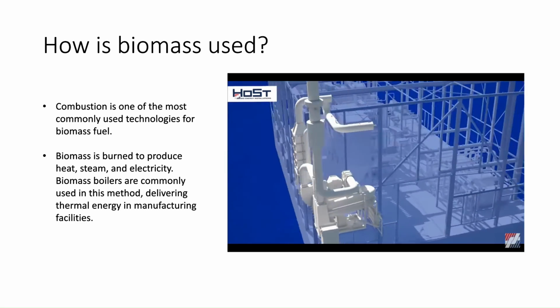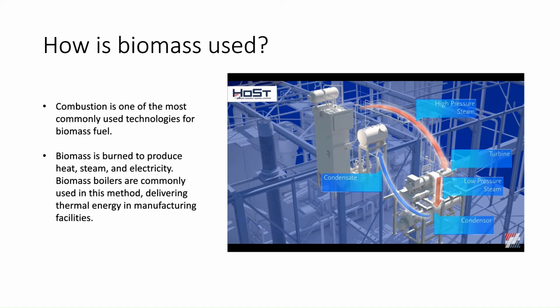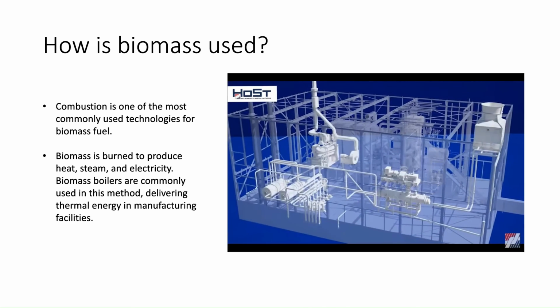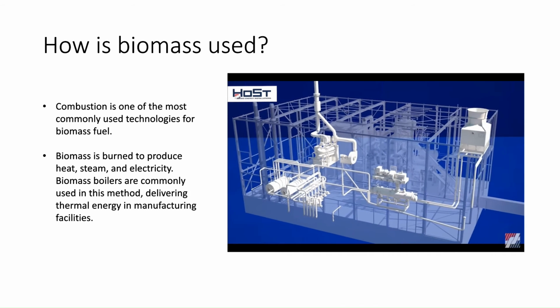The heat the flue gases have given off in the steam boiler is transformed into high-pressure steam, which is led through a pipeline to a turbine. In the turbine, the pressure and the temperature of the steam are converted into shaft power output that is used to drive a generator. After the turbine, the expanded steam enters a condenser, where it is cooled further and condenses, thus generating heat. The heat released from the steam condenser and the flue gas condenser is introduced into the district heating system by means of pumps. 2 gas boilers can be brought online as backup or to meet peak demands for heat. The electricity generated by the generator is fed into the grid as green energy. If there is no heat requirement from the district heating system, the heat from the steam condenser can be cooled via a cooling tower so that the turbine can continue to operate.